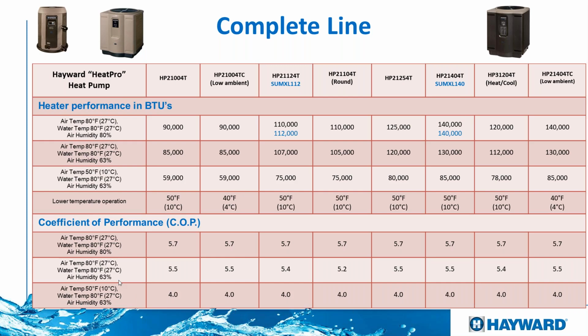What that COP means is that for each kilowatt that the heat pump uses, it is able to produce 5.7 kilowatts of heat into our swimming pool. So it is a very efficient method to transfer heat into our swimming pool. And unlike an electrical resistance heater, where the formula is just 1-to-1, it consumes 1 kilowatt and produces 1 kilowatt of heat, with the heat pump, remember the COP, it consumes 1 and it produces 5.7 kilowatts of heat into our swimming pool. And that is important because it shows how efficient the unit is. That 5.7, if we look at it as a percentage of efficiency, is equivalent to 570%, because again, for every 1 it produces 5.7.